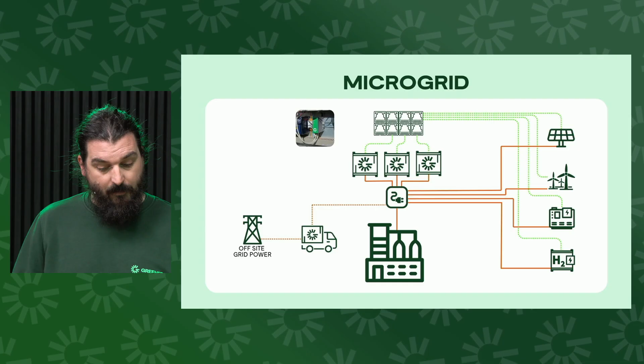Okay. So then we have our basic system running. Grid forming. Yeah. And if there's no grid there, we will have to make the grid ourselves. So that means that the batteries are in a grid forming mode. We are not following anything else because we are the strongest part there, and we are controlling all the other bits to come on, to be switched on and off as the energy demand needs that. So energy optimization being the key there. Absolutely. So looking at prioritizing renewables over certainly fossil. And then going between, do you want to cart it in, or is the fossil still there?